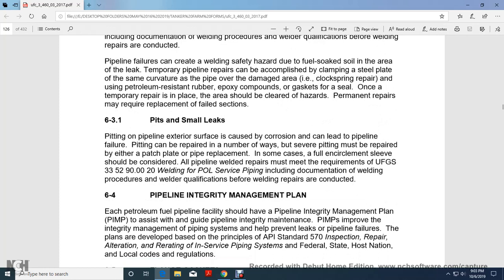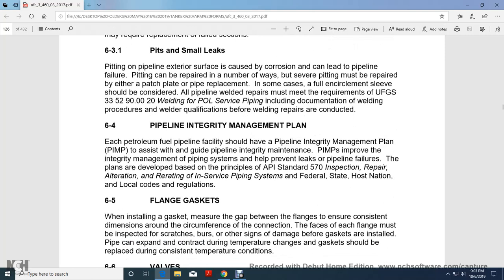Pitting on the pipeline's exterior surface, caused by corrosion, can lead to pipeline failure. Pitting can be repaired in a number of ways. Surface pitting can be repaired either by a patch or pipe replacement. In some cases, a full encirclement sleeve should be considered. All pipeline welding and repairs must meet the requirements of the Unified Facilities Guide Specification. Welding of petroleum, oil, lubricant service pipeline, including documentation, welding procedure, welding qualification, and welding repairs conducted.